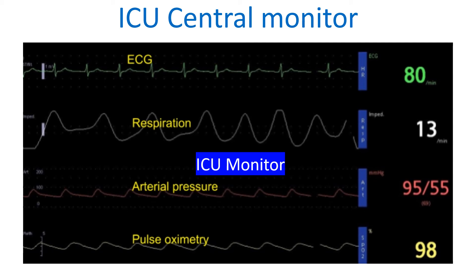Various alarm settings are available for each parameter, and alarms can be disabled if needed in case of a false alarm, either from the bedside or from the central location. Be careful to check the physiological state of the patient before muting an alarm to avoid a catastrophe. Muting of alarms is usually time-limited so that it will unmute itself after a certain period for safety reasons, ensuring a different true alarm is not missed.